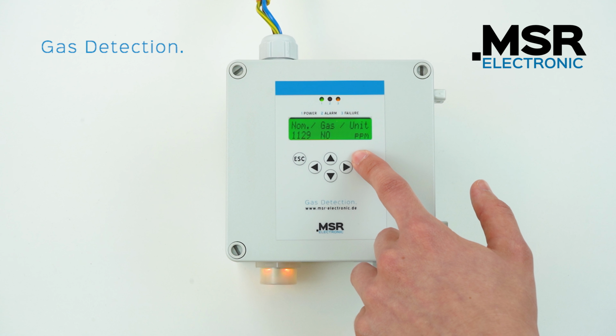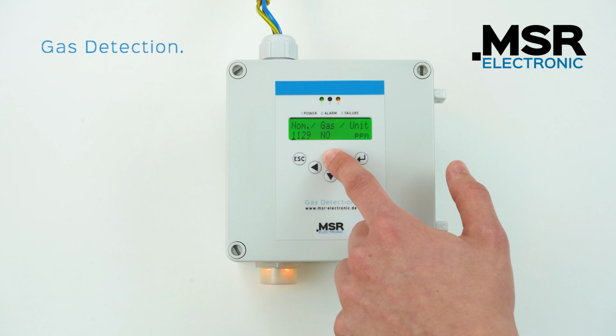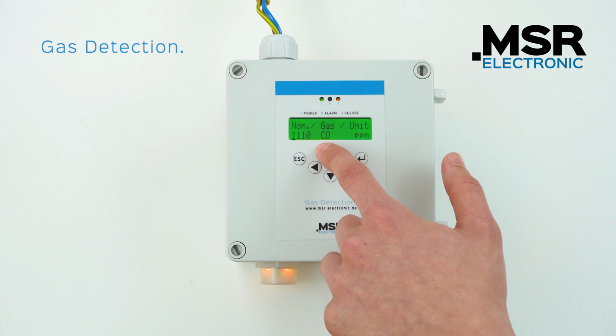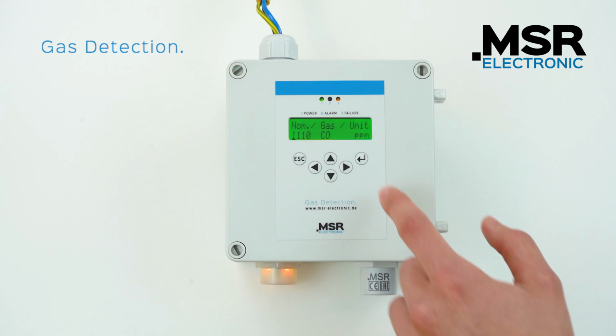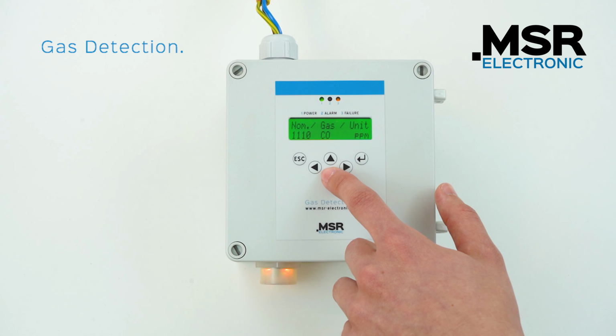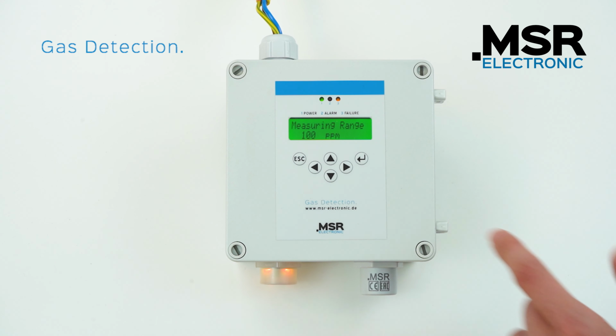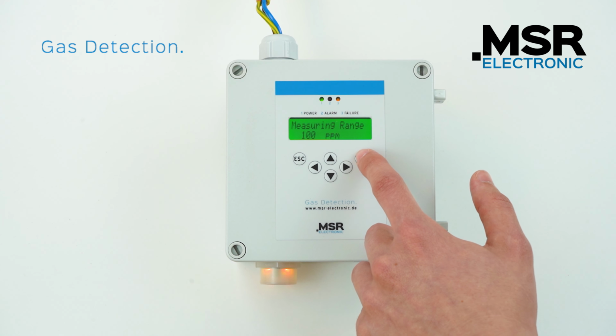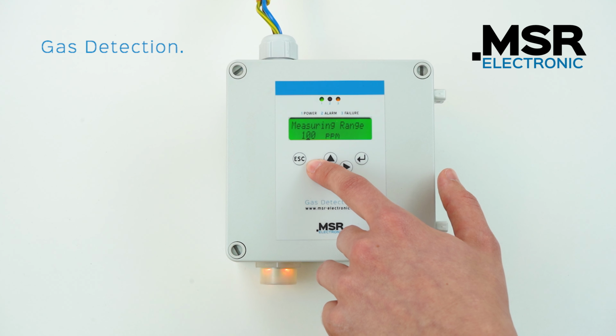Now go to the gas selection and select the correct gas. The respective gas type must be matched with the connected sensor. This can be found on the laser marking of the sensor. Please also check the measuring range for the correct configuration.